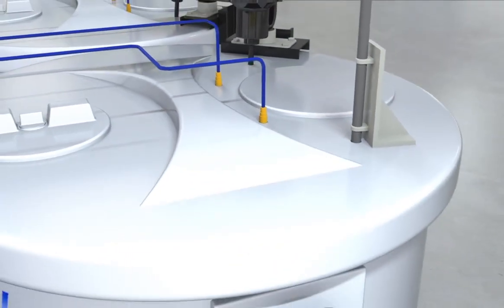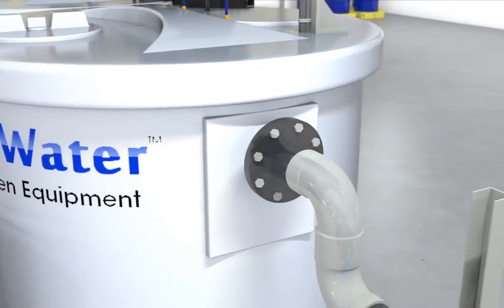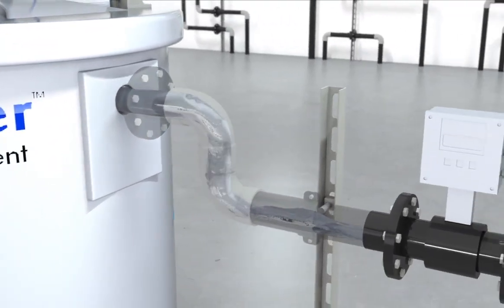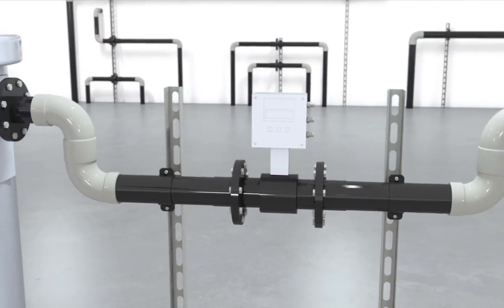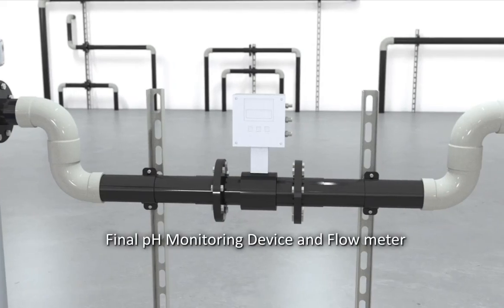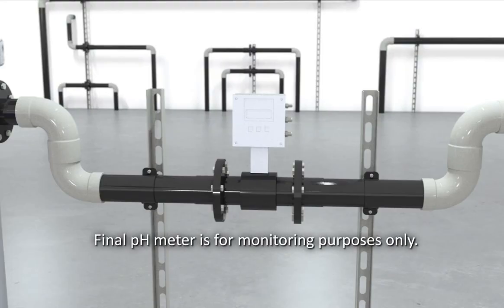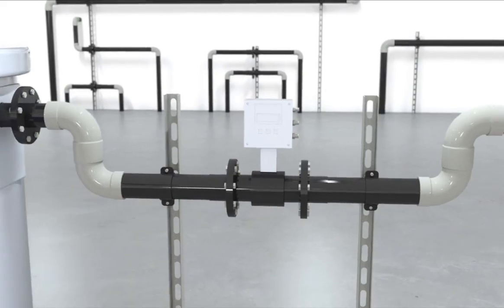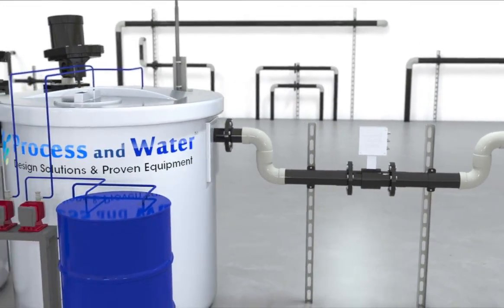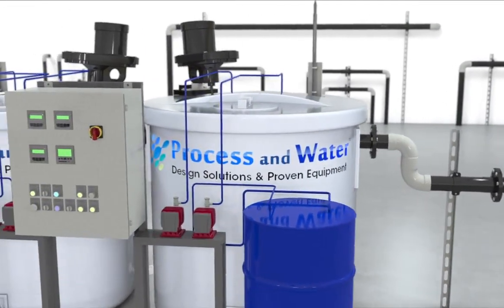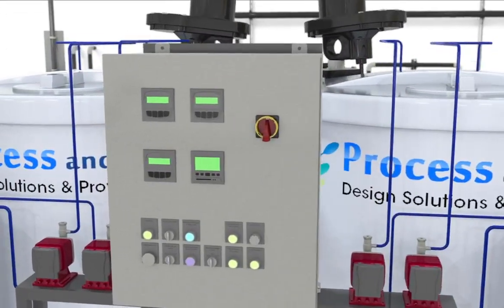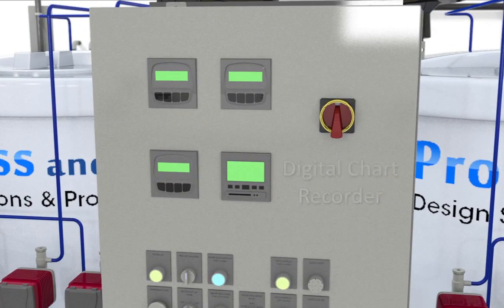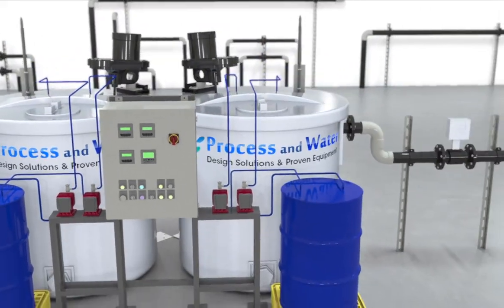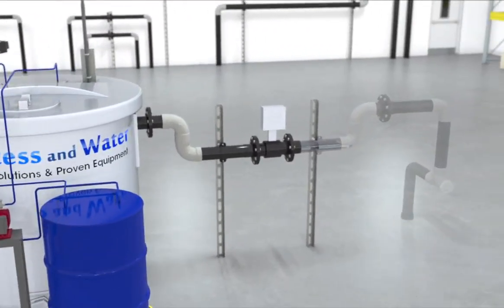The solution continues to agitate as the water cascades over from stage 2 and the treated pH neutralized wastewater is passed under gravity flow conditions to the final pH monitoring device and flow meter. The final pH meter is for monitoring purposes only. No chemicals can be controlled through this meter. The numerical value of the final pH and discharge flow rate are continually and instantaneously recorded on the panel-mounted digital chart recorder. After the pH is monitored, the flow continues through the effluent pipeline, gravity-fed to the sewer.